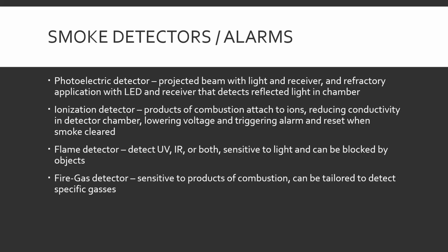So these fire gas detectors are good because you can tailor the detector to the gases you don't want. So if you're in a welding shop and you've got argon or CO2 floating around, these gases can go around this detector, go into this detector, and the detector doesn't care. It's not looking for that. Same with the foundry and molten metal, whatever gases might be coming off of that floating around the air, the gas detector doesn't care. It's not looking for it. But it'll go off when gases that it's supposed to be looking for are there. So those are harder to fool. They won't go off unless, like I said, what they're looking for is there.